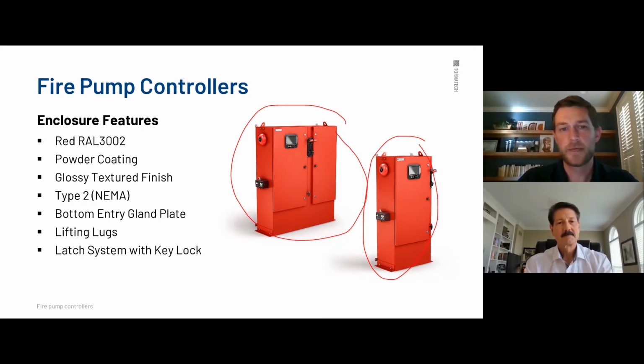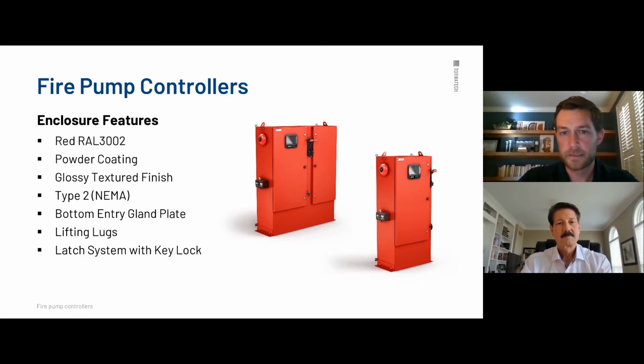These are what we call our size 2 panels. Size 2 and up does not have legs. So this area down here below is what we call the wire bending space. Every one of our panels comes with this bottom entry gland plate, which we'll have a picture of later on. We recommend that you come in through that bottom entry gland plate, not the top. If you can't go through the gland plate, the other recommendation would be to come in through the side down here. If you can come in through the bottom side, either side would be fine. Top entry is going to be your very last option if there's no other way. We prefer that bottom entry gland plate. We also come standard with these lifting lugs and a wall mounting system too. It's kind of hard to see these little tiny gray things that you can wall mount over, all the panels. And then the big red ones, those are the lifting lugs.